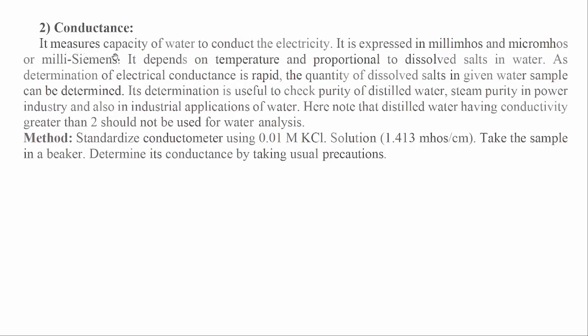2. Conductance: It measures the capacity of water to conduct electricity. It is expressed in millimhos, micromhos, or millisiemens. It depends on temperature and is proportional to dissolved salts in water. Since the determination of electrical conductance is rapid, the quantity of dissolved salts in a given water sample can be determined. Its determination is useful to check purity of distilled water, steam purity in the power industry, and industrial applications of water. Note: distilled water having conductivity greater than 2 should not be used for water analysis. Method: Standardize the conductometer using 0.01 M KCl solution (1.413 mhos/cm), take the sample in a beaker, and determine its conductance by taking usual precautions.